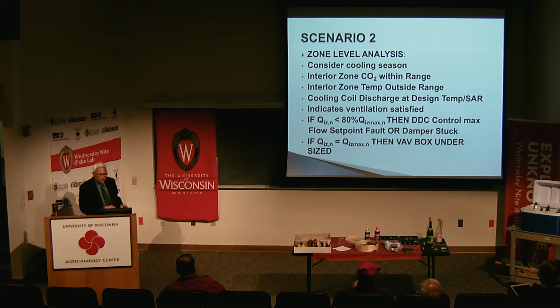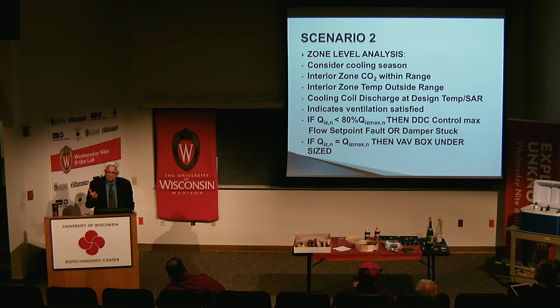Or the flow rate could be at maximum flow rate, but yet the temperature is not satisfied. In this case, the variable volume box itself is undersized. When it is undersized, you don't get the maximum flow. So the fault detection identifies three scenarios for the operator to look at. Look at the DDC controller for the maximum flow set point. Look at whether the damper is stuck. Look at whether the VAV box is undersized, so that you can take action.